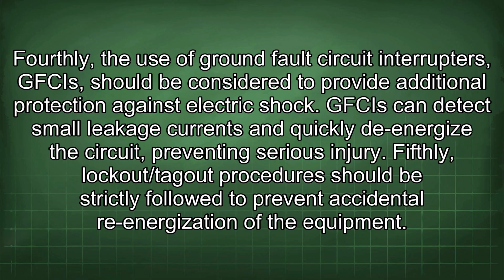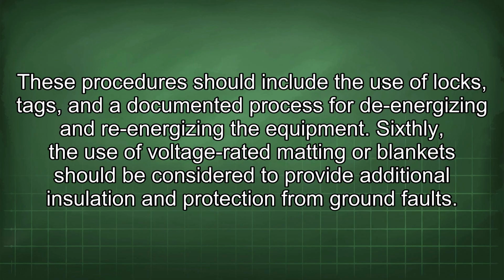Fourthly, the use of ground fault circuit interrupters, GFCIs, should be considered to provide additional protection against electric shock. GFCIs can detect small leakage currents and quickly de-energize the circuit, preventing serious injury. Fifthly, lockout/tagout procedures should be strictly followed to prevent accidental re-energization of the equipment. These procedures should include the use of locks, tags, and a documented process for de-energizing and re-energizing the equipment.